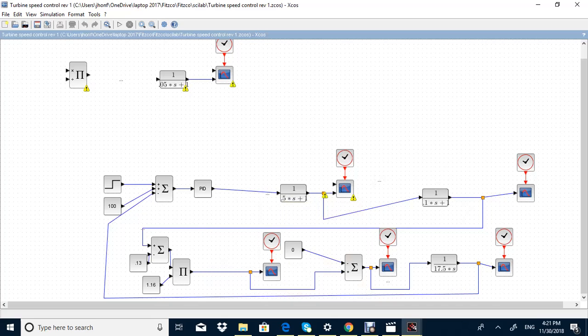So let's give it a run and see what we do. Now, there's no starting means in this, is there? So I just put fuel into it, and the turbine speed comes to 100%. So that's not a realistic model at all. But that's only the first 20 seconds. You're going to see the fuel overshoot, and the speed goes to full speed in 20 seconds. Then after that, I'm going to have a 1% speed change, and you'll see a little bump down. This is an incomplete model. There's some things I have to change, but let's give it a shot and see what we can do.